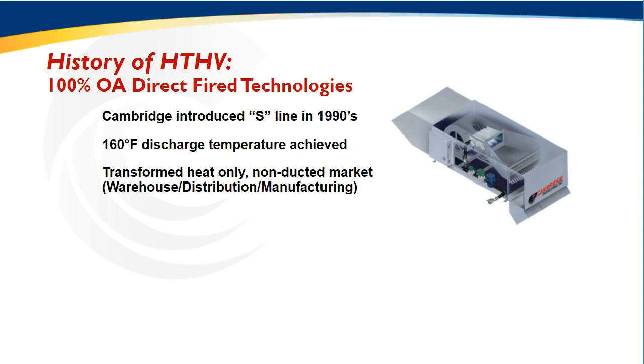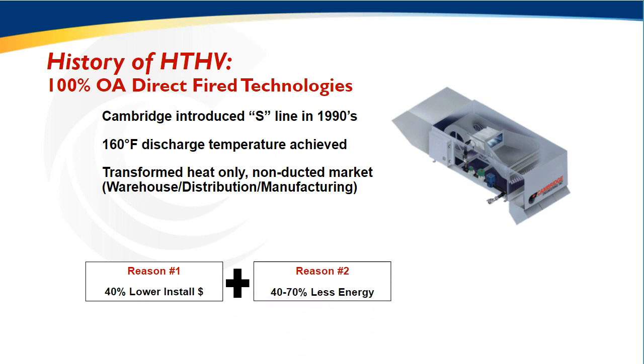And what early adopters saw is that they could lower their install costs by over 40% by utilizing larger systems, by utilizing larger zones, and ultimately greatly reducing the number of installed units from anywhere from maybe 30 to 40 systems down to 6 to 8. Additionally, end users saw their energy bills cut in half. The benefits of the high temperature heat and ventilation systems and pressurization saw that not only were they paying less upfront for their HVAC systems, but ultimately the operating cost of these buildings was greatly reduced over time.